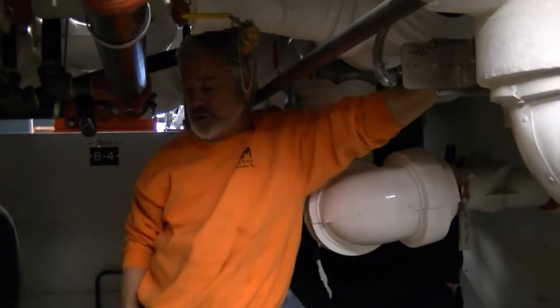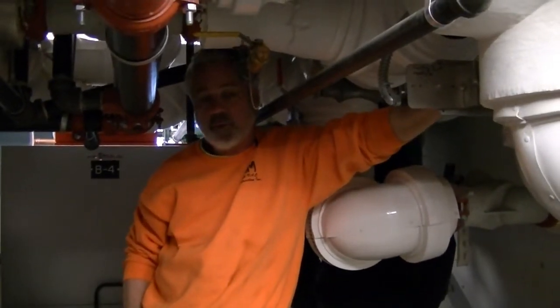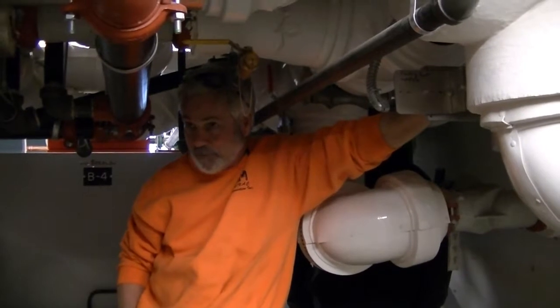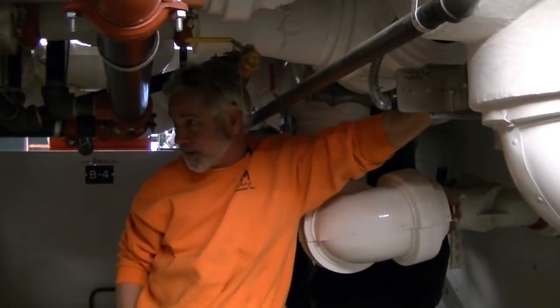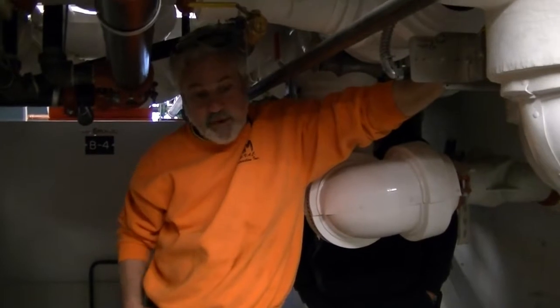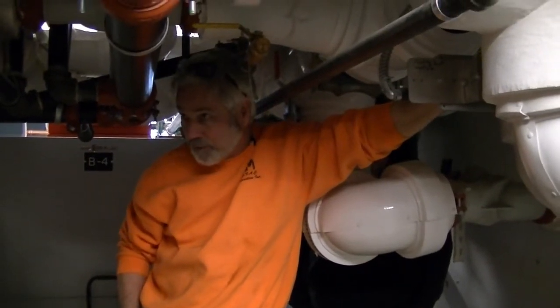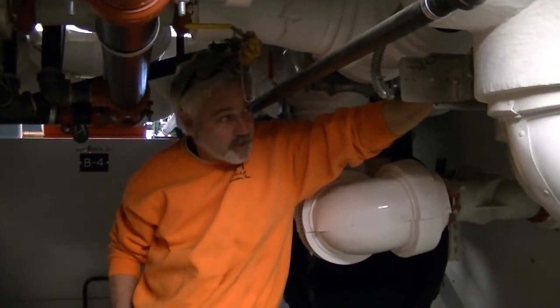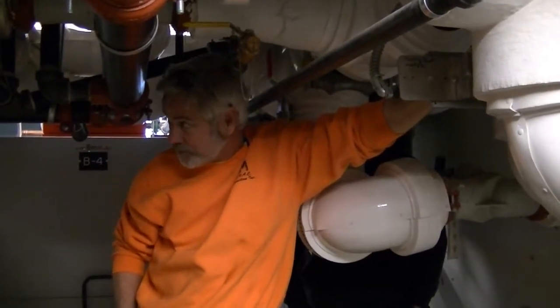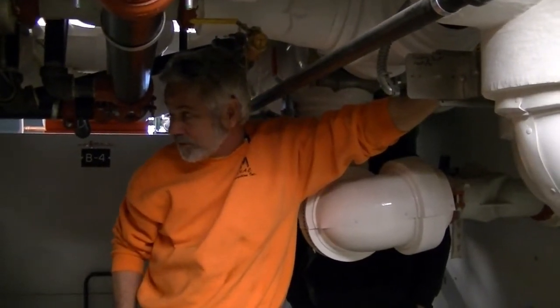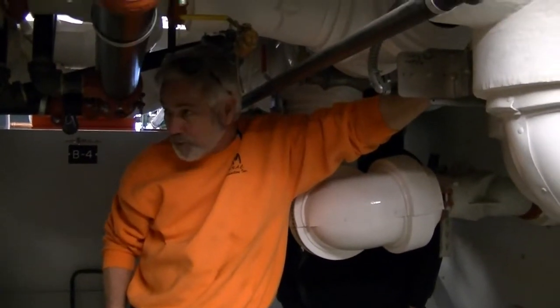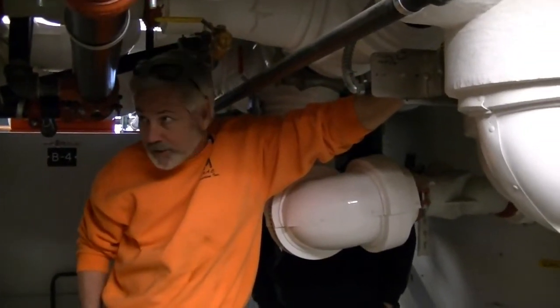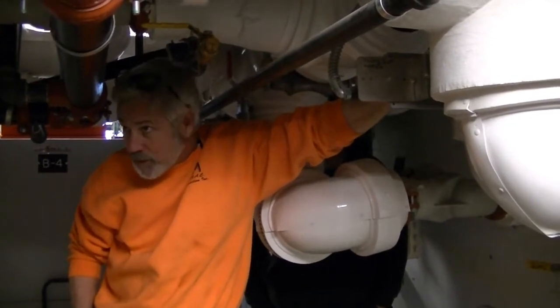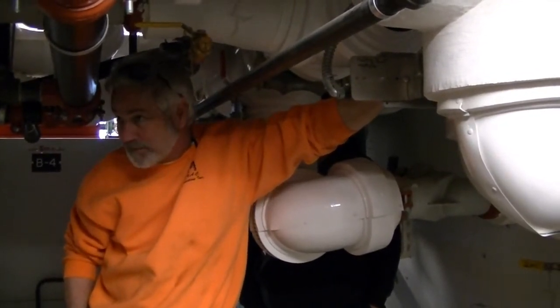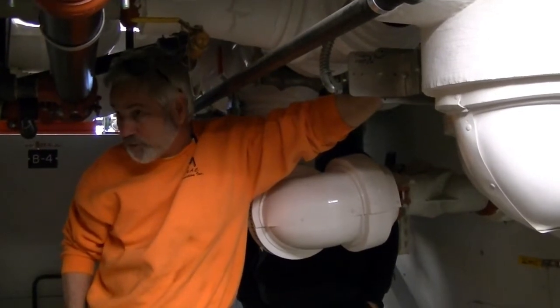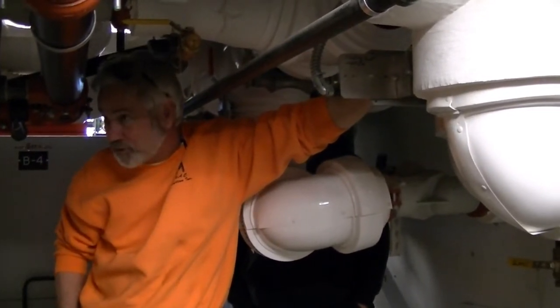As far as the condition of the rooms is concerned, you want to try to keep these rooms as free and clear of dust and debris as possible. Okay, you have to remember that when the boilers fire up and they're running, whatever's in the air here is what they're ingesting. So, no paint fumes, no detergents, no cleaners, no strippers, no wax, nothing. If you can smell something in the air, that means it's not supposed to be there.